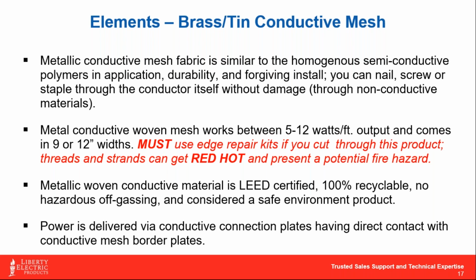The big thing with these is that when you terminate either product, the self-reg polymer or the conductive mesh, you have to take very good care on the termination plates that adhere to them. There can't be any loose ends, loose connections, or hair-like strands hanging off, because they can get very hot, to the point of ignition.